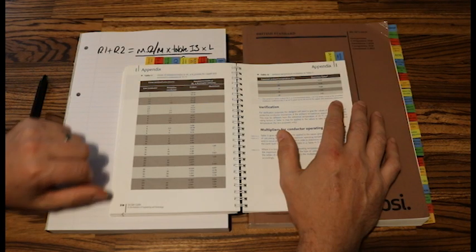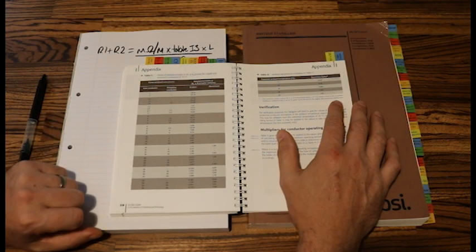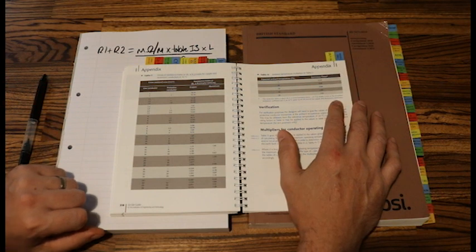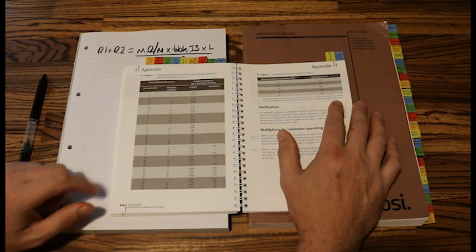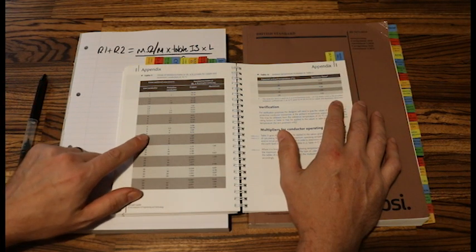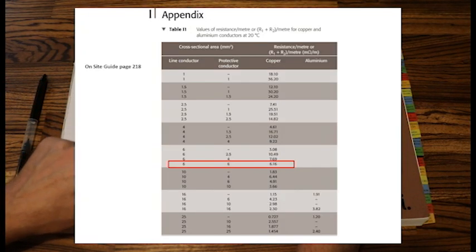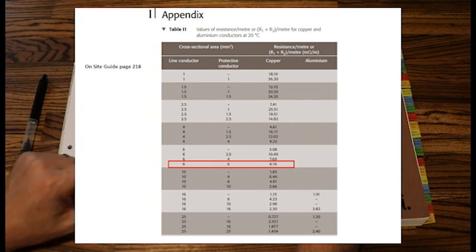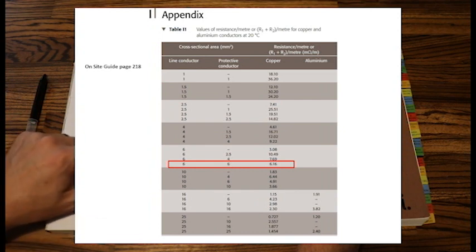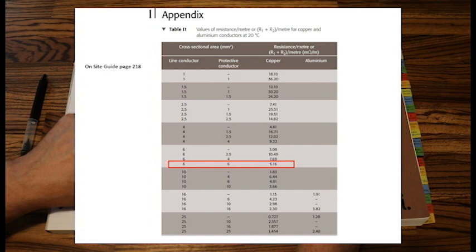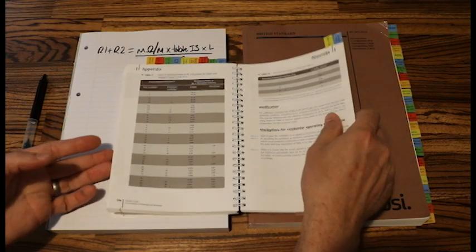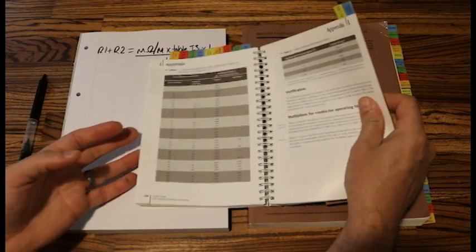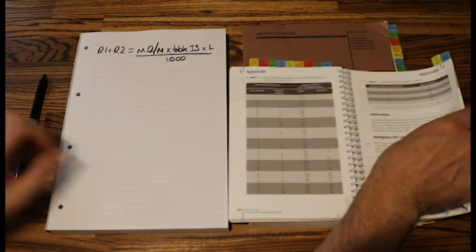So my first question I calculated that I would use a 6mm live. So therefore I've sized the earth to the same. So I have 6mm live, 6mm earth. My milliohm per metre value for this question would be 6.16.